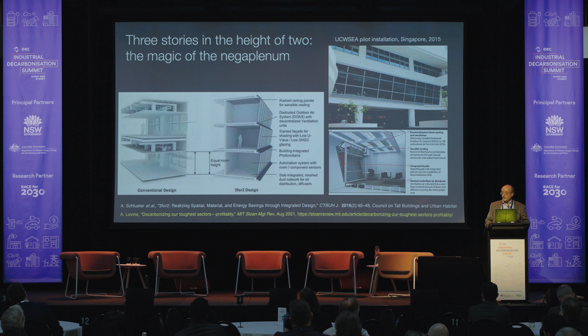55%. How do you do that? Well, you design out the vertical meter of mechanical plenum at each story that you see at the far left, and then within slabs, you can fit 3 stories with unchanged 2.8 meter ceiling height into the current height of 2 stories. Cost, complexity, and time fall dramatically. Why would you do it any other way once you see that?